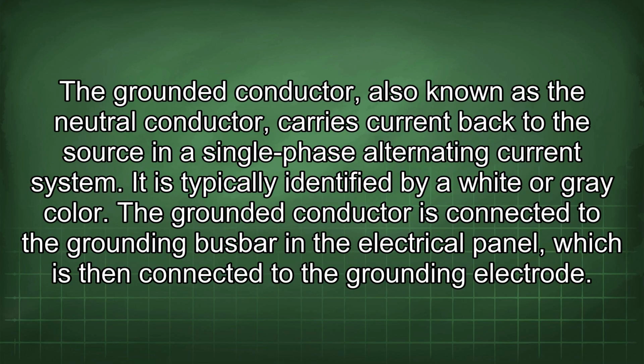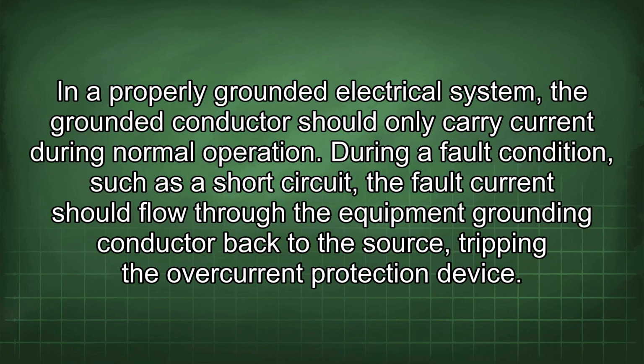The grounded conductor, also known as the neutral conductor, carries current back to the source in a single-phase alternating current system. It is typically identified by a white or grey color. The grounded conductor is connected to the grounding busbar in the electrical panel, which is then connected to the grounding electrode. In a properly grounded electrical system, the grounded conductor should only carry current during normal operation. During a fault condition such as a short circuit, the fault current should flow through the equipment grounding conductor back to the source, tripping the overcurrent protection device.